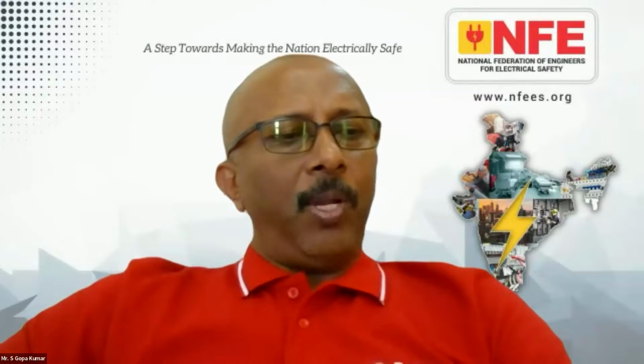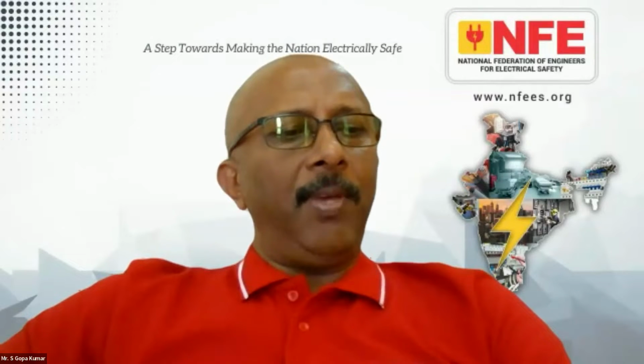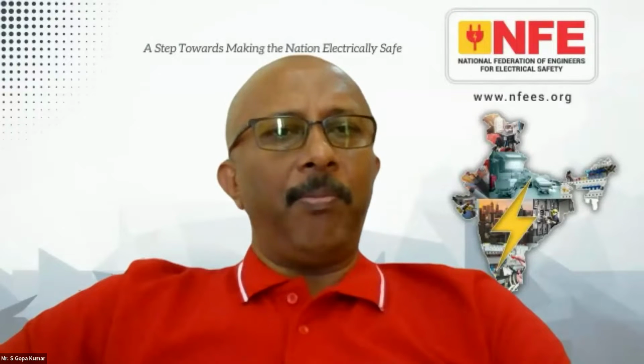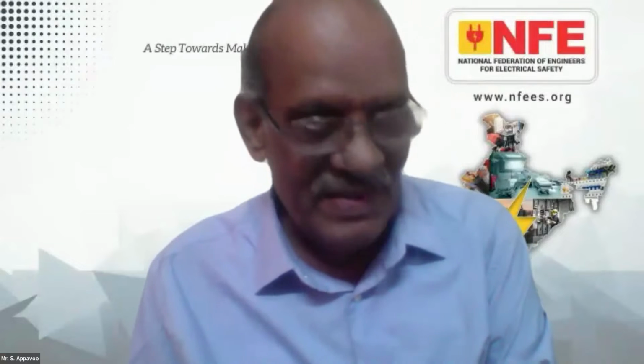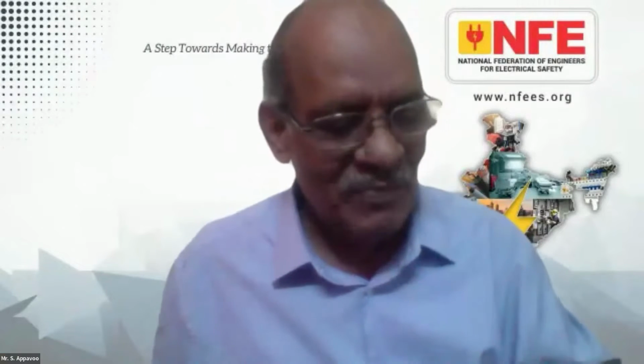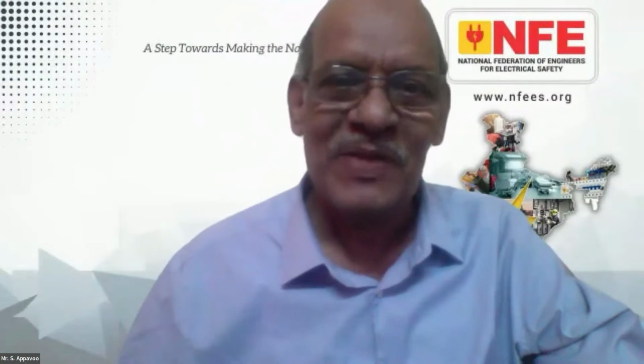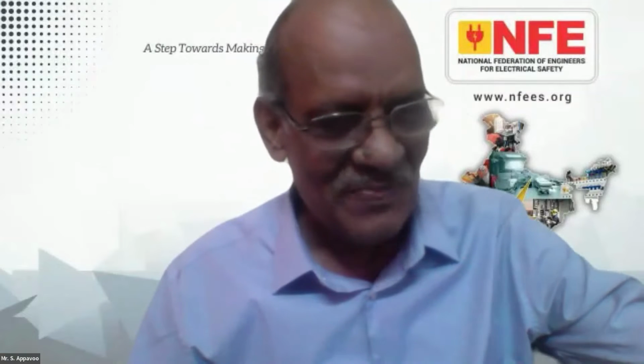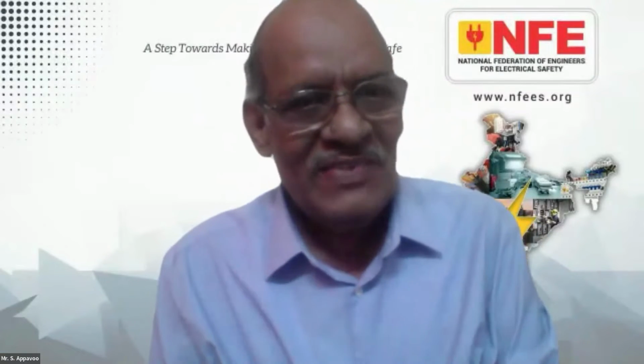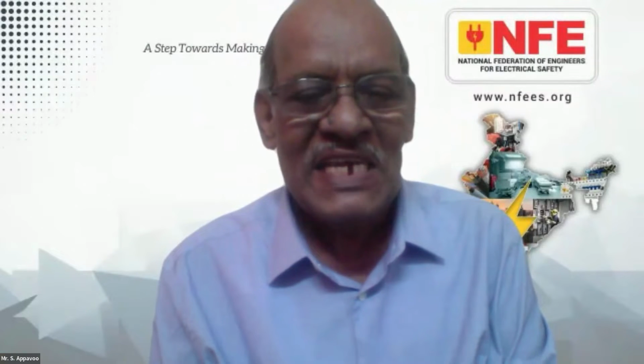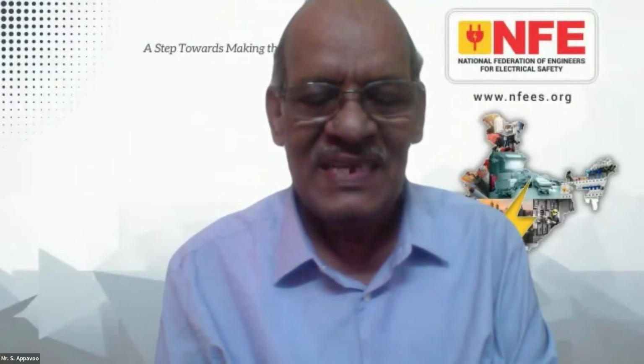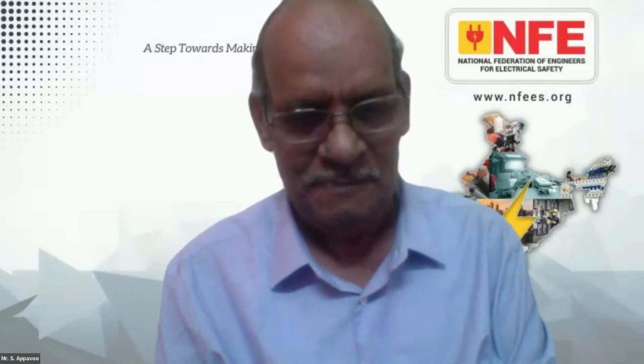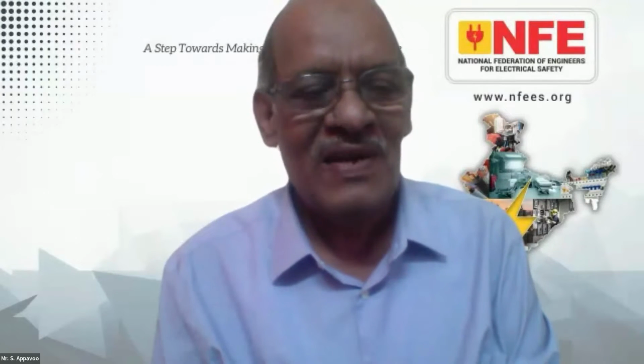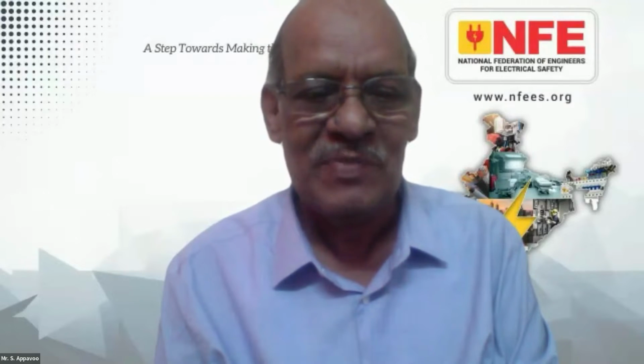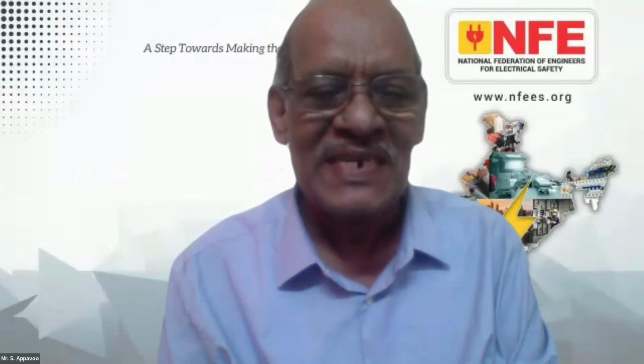Next question is to Apav sir. Sir, what is PCC and what is the role of ISC and IL in arriving at an effective methodology for implementation by the DISCOM? Good morning, everybody. It's a very valid question because ultimately people are bothered about the mitigation against the statutory implementation. So here come two important parameters. That is ISC, I short circuit, which is based on the fault level at which the consumer is fed from the distribution substation or the public utility substation. Another is the IL. Haribala has already explained it as the annual average demand level. So these two things are totally changing the scenario of implementation and mitigation.